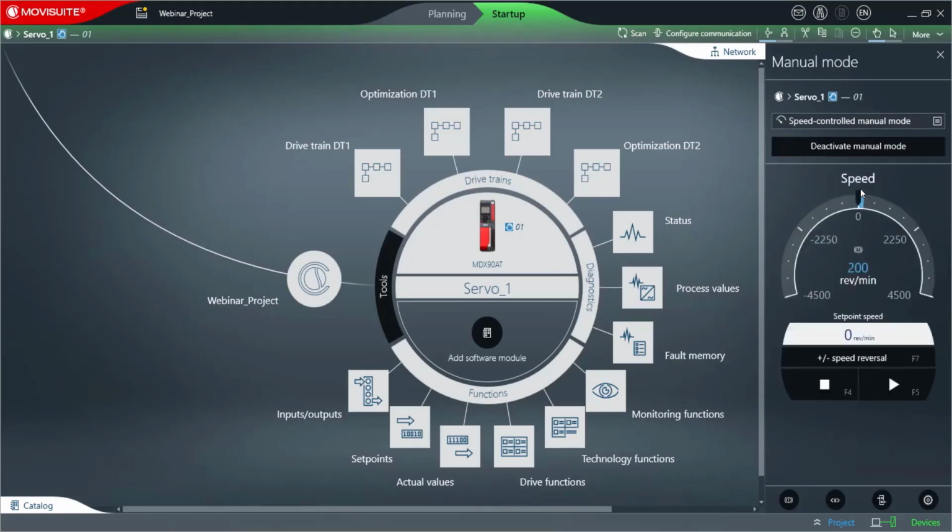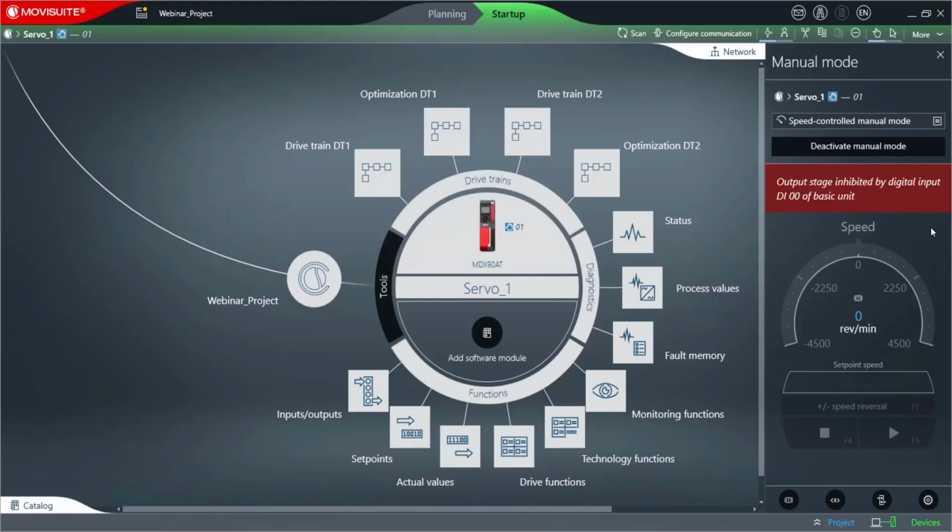So I'm going to click activate manual mode, and you notice it pops up a big red warning and says I can't run the motor because the output stage is inhibited by digital input DI00. This is pretty much a standard feature on SEW products, that digital input 00 is permanently assigned to the controller inhibit function. So if DI00 is off or at ground level, then the VFD is inhibited.